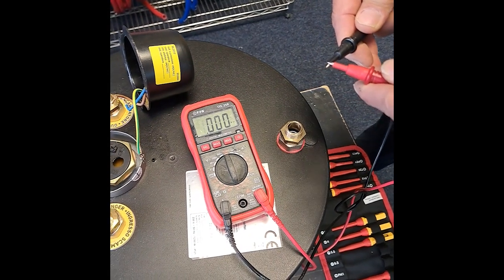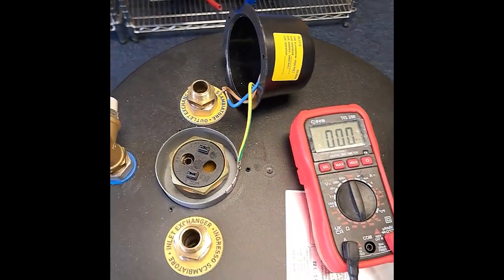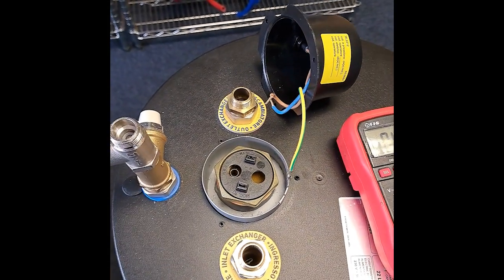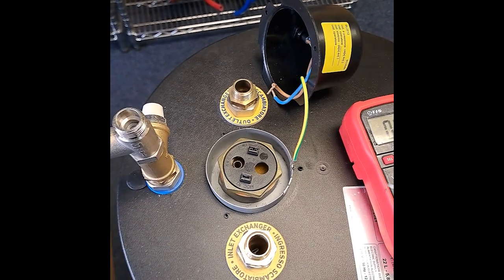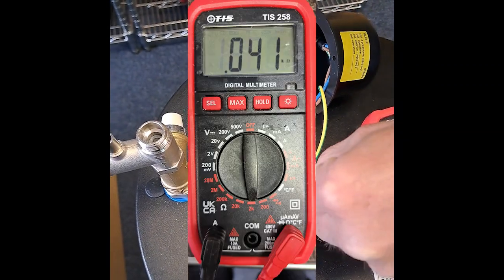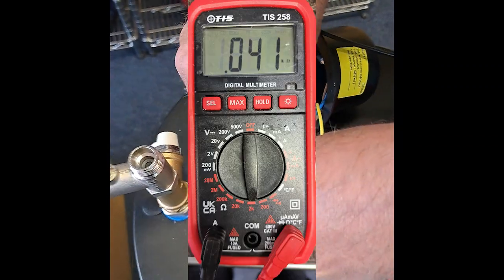Now we're going to test the element, which we've made sure has been disconnected from the power supply. We'll place the probes on the terminals, and we can see here a reading of around 40 ohms. This shows that the element is working fine.